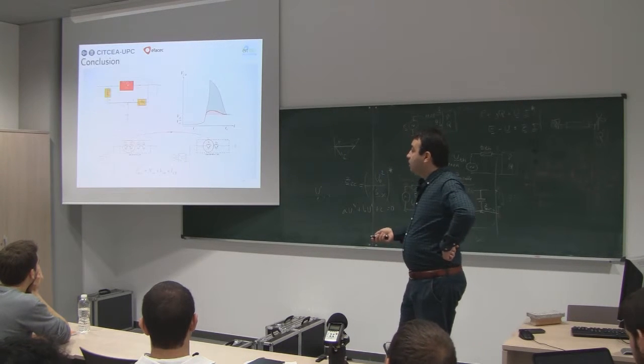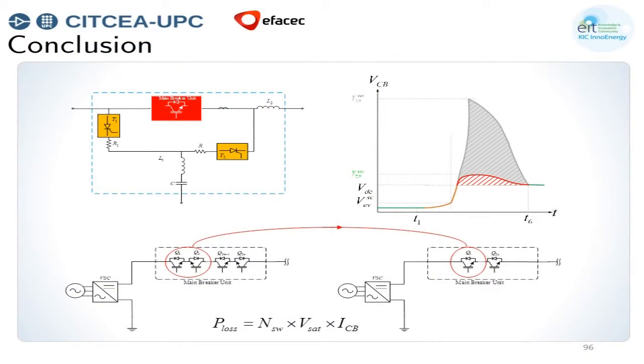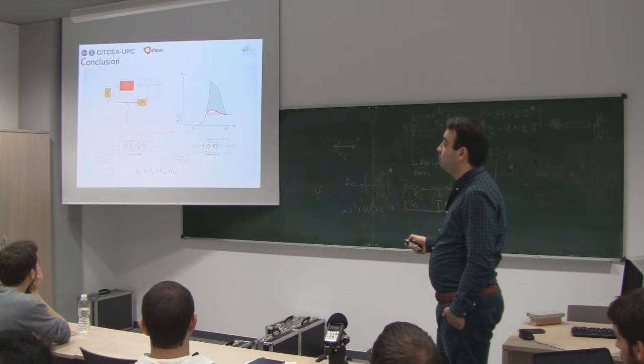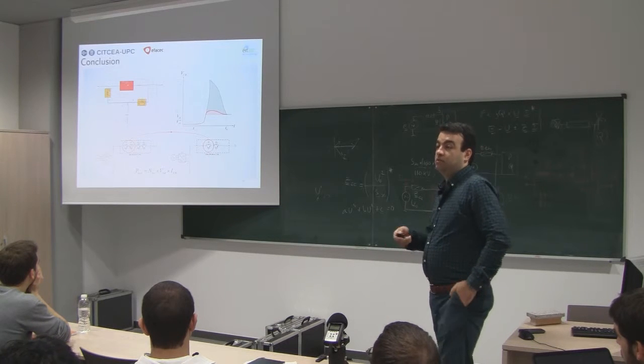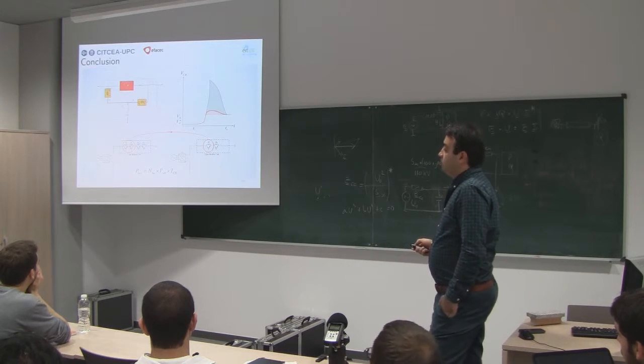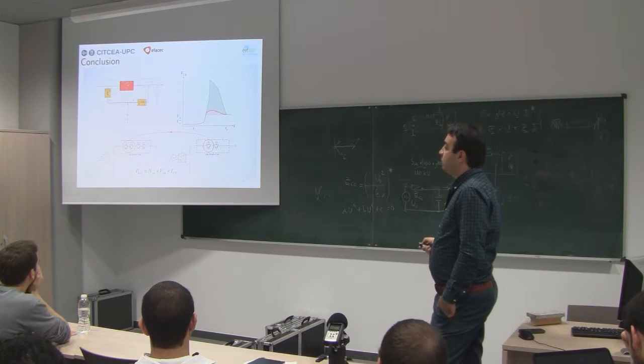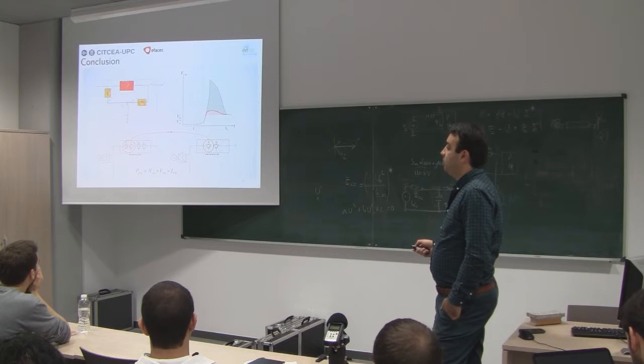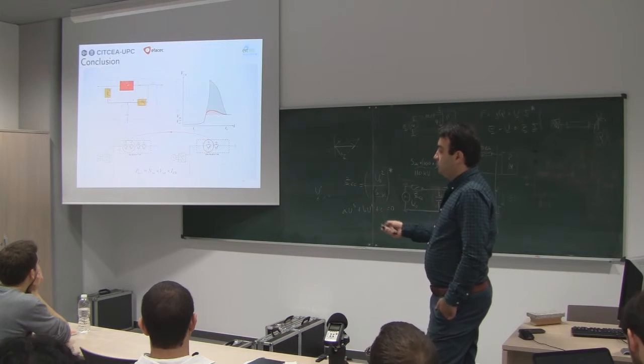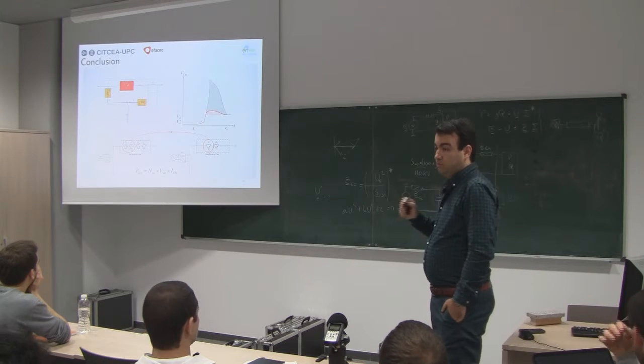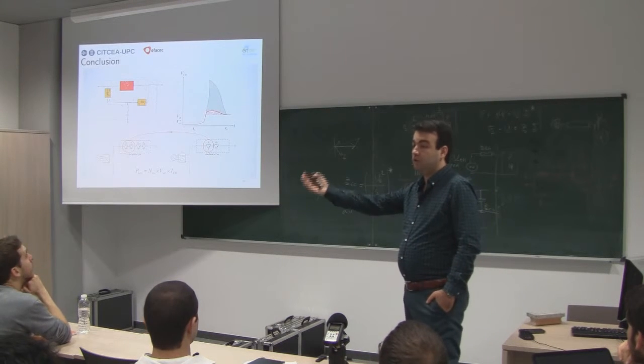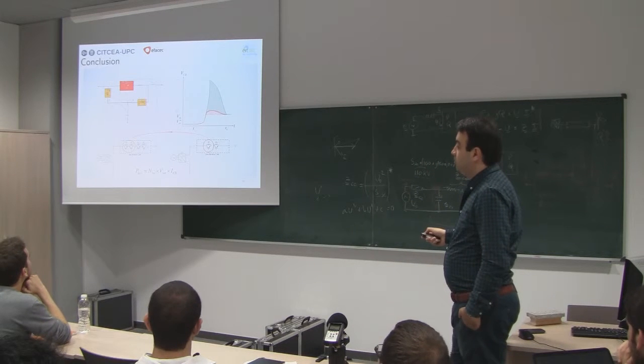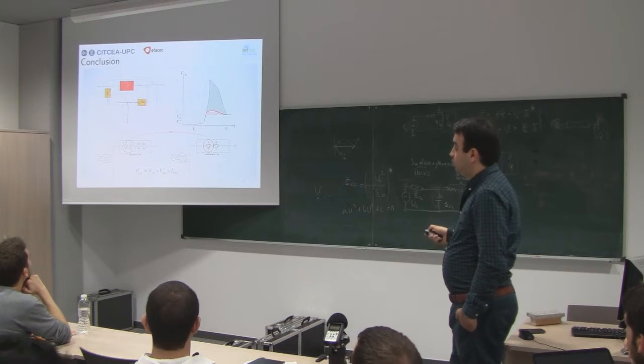and it has no impact on the converter. So just as a conclusion about the last part of the discussion that I introduced, with this topology we may be able to decrease the transient overvoltage very effectively without using the parallel surge arrestors, and it is expected to have less power losses. As I told you, we replaced a couple of IGBTs with one IGBT, but this idea is not from us, it is adapted from some other applications to this application. But the main idea that we have developed is this branch.